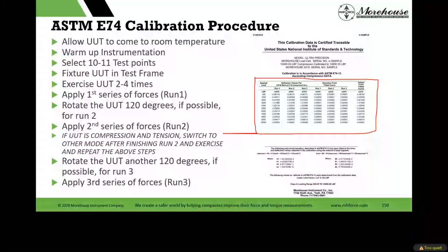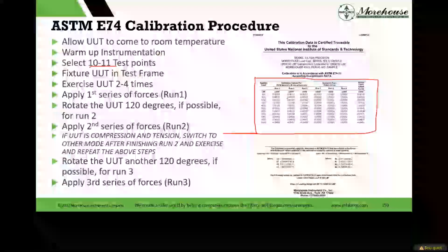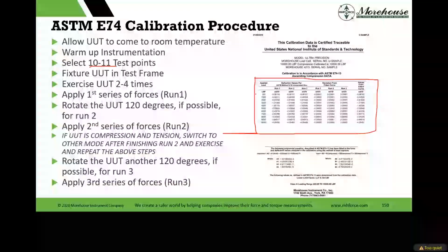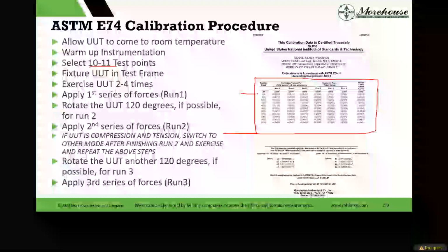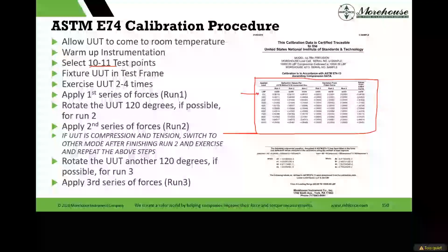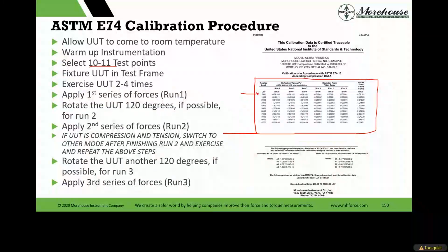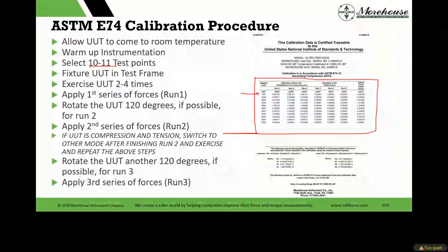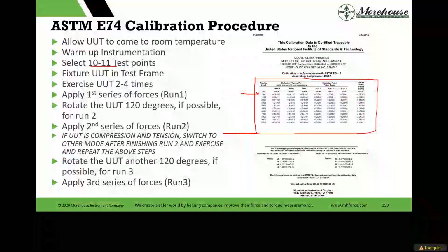Warm up the instrumentation, that's hook it up to your meter. Select 10 to 11 points. The standard's very descriptive in that you cannot use it below the first calibrated non-zero point. So the reason I say 11 points here is most people out there doing field work do not like substituting load cells that much, because if you can use 1 load cell instead of using 2, your cycle time in calibrating the machine is a lot easier than if you have to change out 2 or 3 load cells.